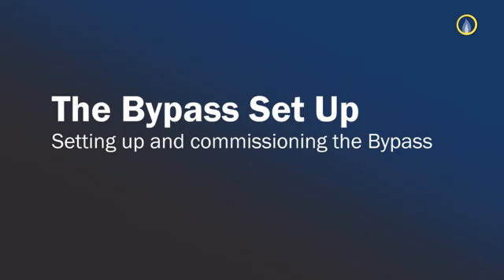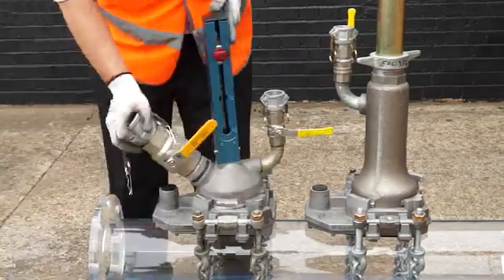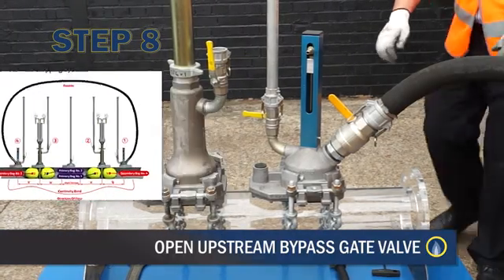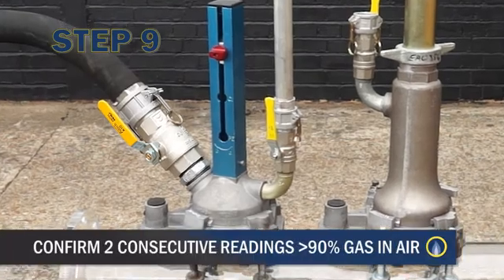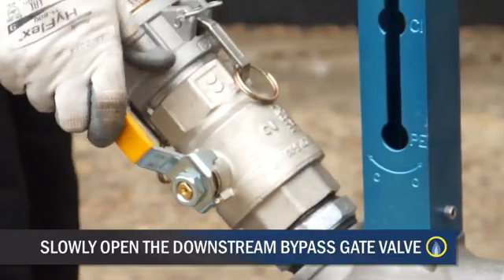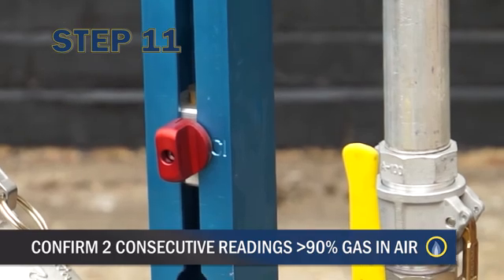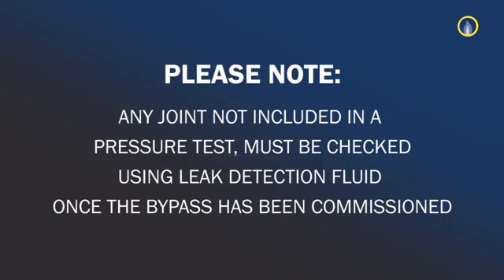Setting up and commissioning the bypass. Ensure that the pressure gauges or recorders are working and fitted correctly, showing current pressure in the main. Open the vent valve on the downstream side of the bypass. Slowly open the upstream bypass gate valve on the bag stop base and allow gas to vent out at the downstream vent position. Confirm two consecutive readings of greater than 90% GIA and close the vent valve. Close the upstream bypass gate valve. Open the upstream bypass vent and slowly open the downstream bypass gate valve. Confirm two consecutive readings of greater than 90% GIA from the vent and close the upstream bypass vent. Reopen the upstream bypass gate valve. Any joint not included in a pressure test must be checked using leak detection fluid once the bypass has been commissioned.